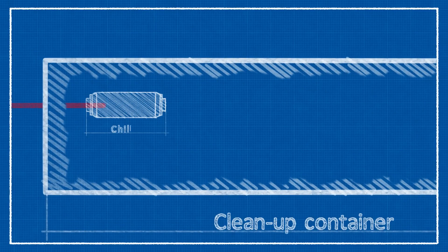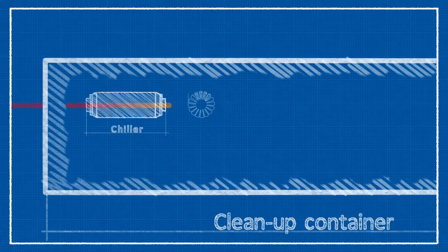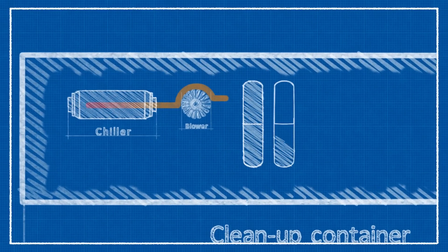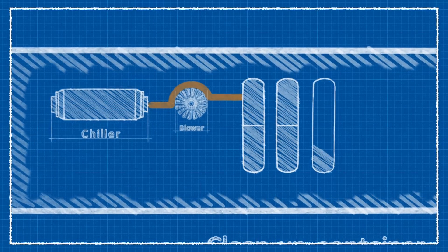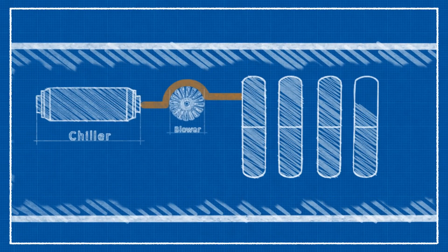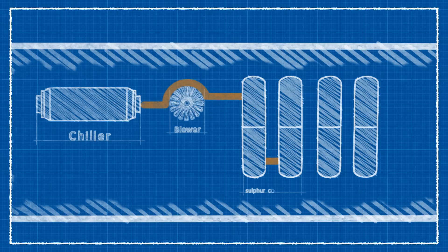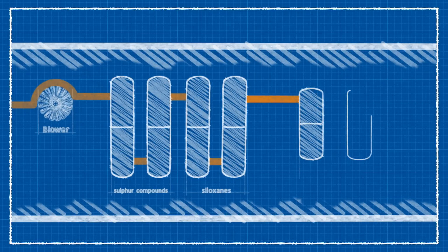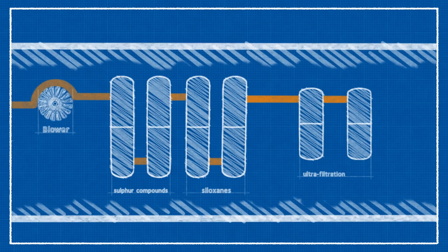Biogas is first dried with a chiller, and then pushed through an absorption cleaning system with a blower. The clean-up is developed with a lead and lag configuration, composed of two series of reactors, selective on sulfur compounds and siloxanes. An ultra-filtration lead and lag system is also available.